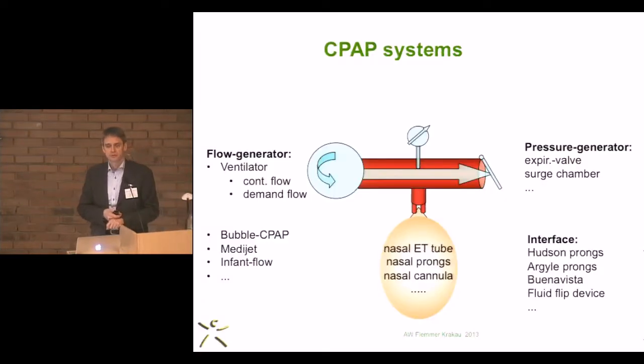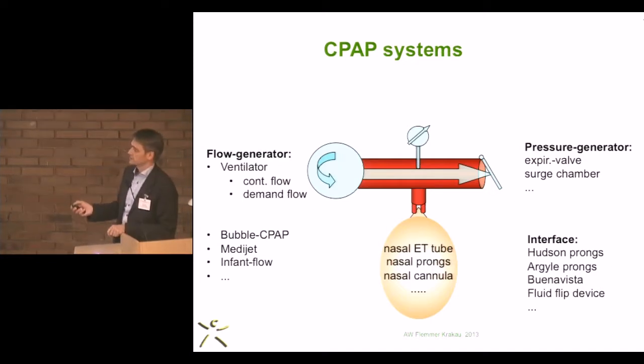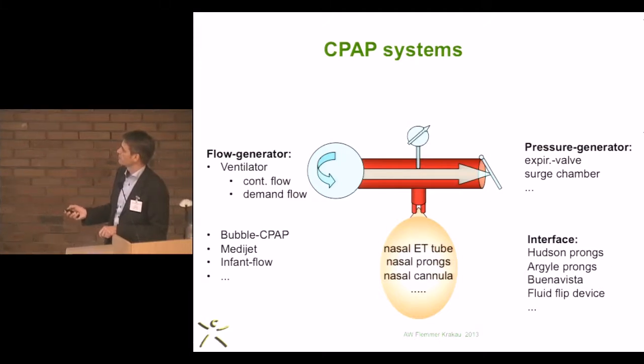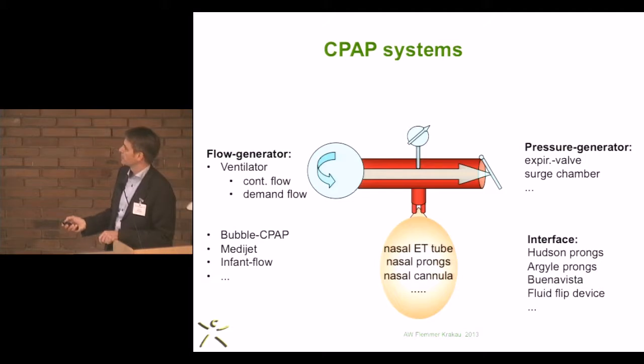Now, when we go back to the CPAP systems we are using, it's all more or less the same. We have a device that generates flow. If it's a ventilator, it's going to be continuous flow or demand flow, or we have a flow source with a continuous flow from the wall going into a bubble CPAP. We have MediJet or others, and we have infant flow. And we can measure pressure at the airway opening, and pressure is actually controlled by an expiratory valve. That could be a chamber with water, like in the bubble CPAP, or the valve in the ventilators, or the devices that are used. And the other thing we just saw also is the interface. You've seen Peter's slides with Hudson prongs. There are other prongs. You can use an endotracheal tube just put into the nose, or other nasal cannulas.